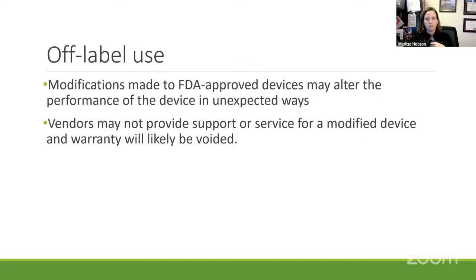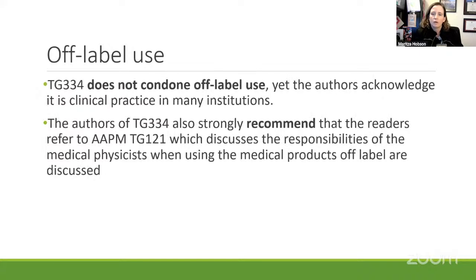So you need to consider the mechanical integrity, because one screw may not be the same in terms of what load it can hold, the general safety and MR safety of the device. If the status is determined to remain or become MR conditional, the user must establish and document the updated conditions for safe use of the modified device prior to clinical use. So just one thing is that we as authors of the task group 334, we can't condone off-label use liability-wise, but we acknowledge it is clinical practice in many institutions, even our own.